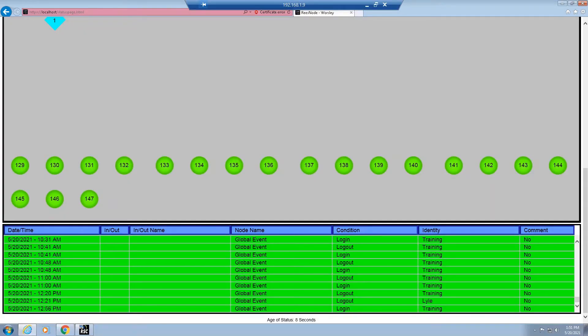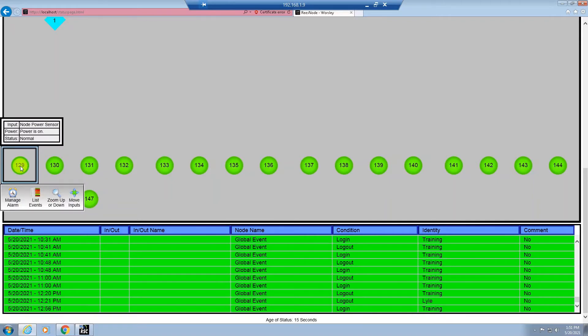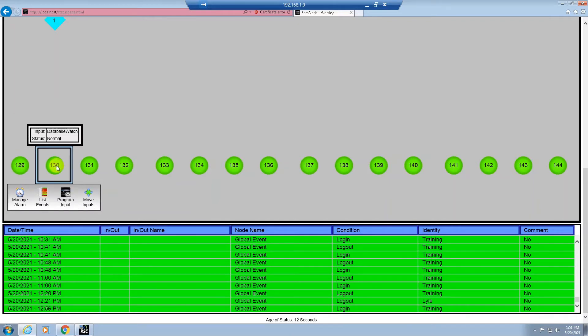At the bottom of the web window you will find system status icons. Input 129 is used to monitor the power on the system, but this is only for individual computers and not normally set up for servers. If your system is on a server, most likely you will not see this input. Input 130 is to monitor the database. If the database is getting full or it has lost communication with the network, this input will go into alarm. You will need to contact your IT department to see if there is a network issue.